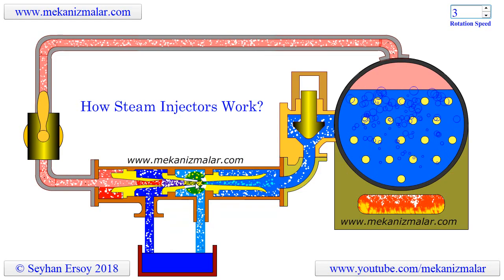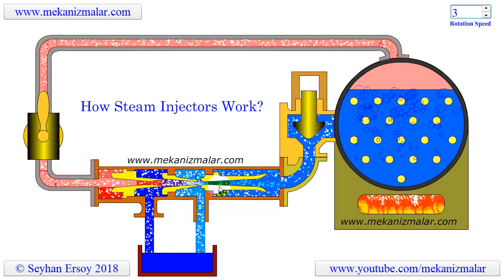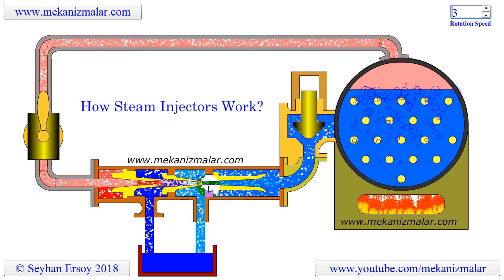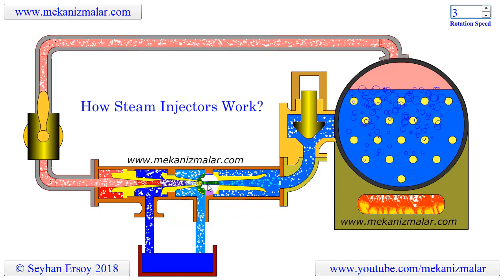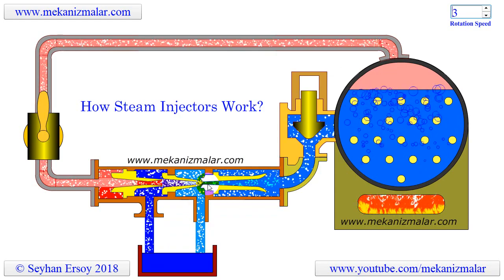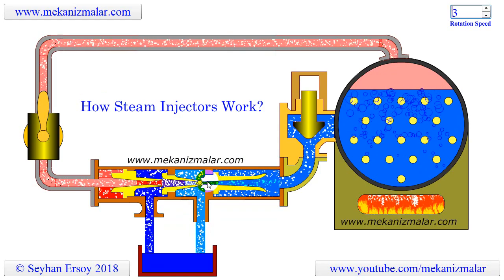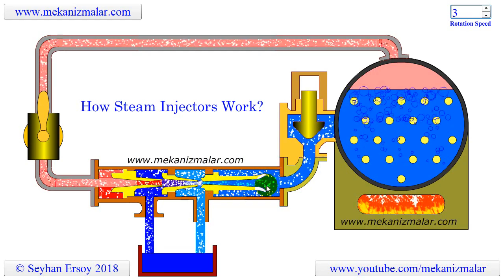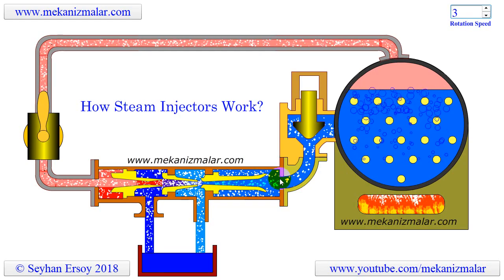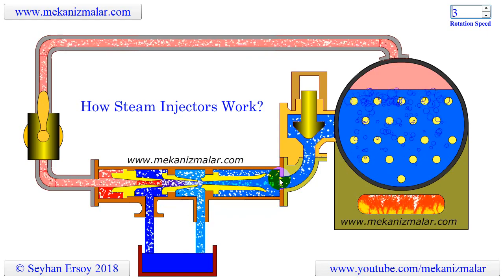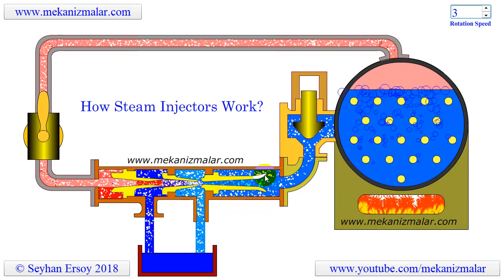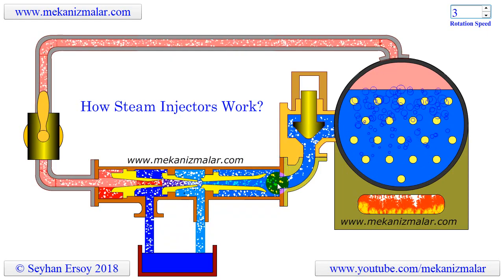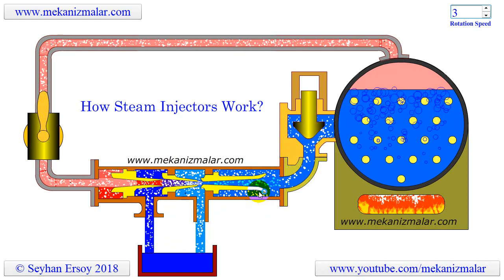The water jet leaving the combining cone is pushed into the delivery cone. It is called the delivery cone because it leads the flow toward the boiler. Before water reaches the boiler, the flow velocity is reduced due to the diverging shape of the delivery cone. Reduced water speed increases the water pressure above the boiler pressure, which allows the feed water to be delivered to the boiler. This flow is shown here in sky blue.